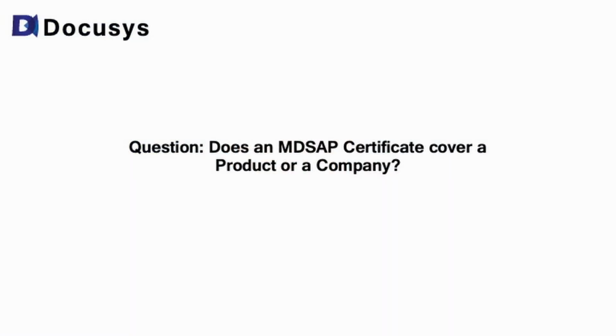The second question is, does an MDSAP certificate cover a product or does it cover the company? The answer is both. Your MDSAP certificate covers the scope of the operations that you do, and it should mention the products that you want to license.